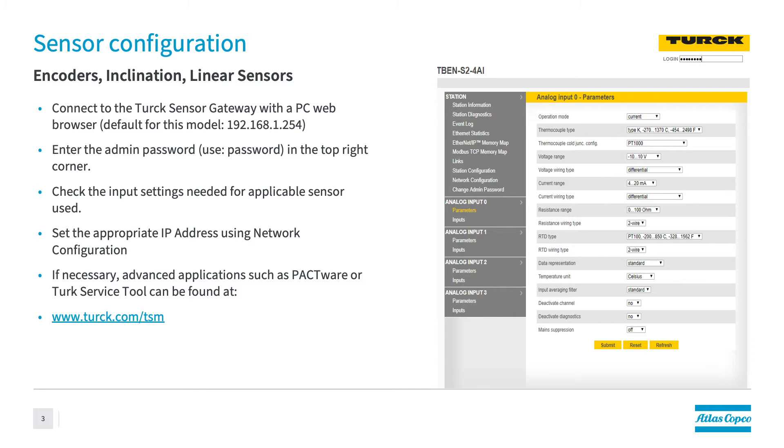On the first screen that you see, you're going to have a couple key things that you have to go in and do. For operation mode, you're going to make that current. As you follow down, you're going to put input averaging filter as standard and deactivate channel no. Once you've completed these three steps, you're going to go into network configuration.